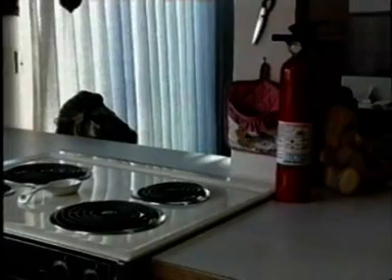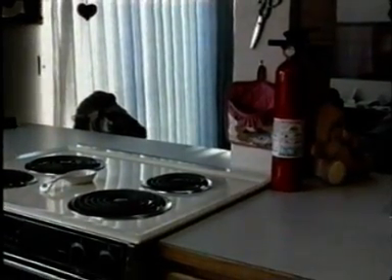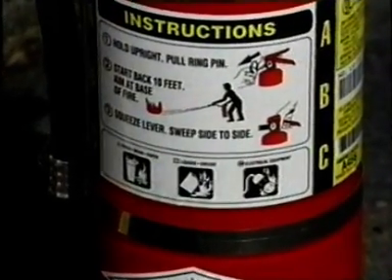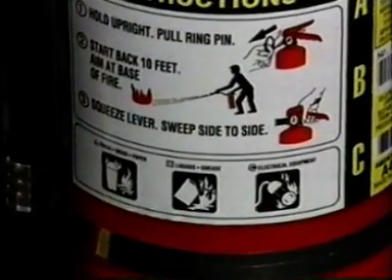Many extinguishers have multiple classifications and ratings. A common portable extinguisher found in occupancies is a 2A 20BC type. This multi-purpose extinguisher can be used on ordinary combustibles, on flammable liquids, and on electrical equipment.